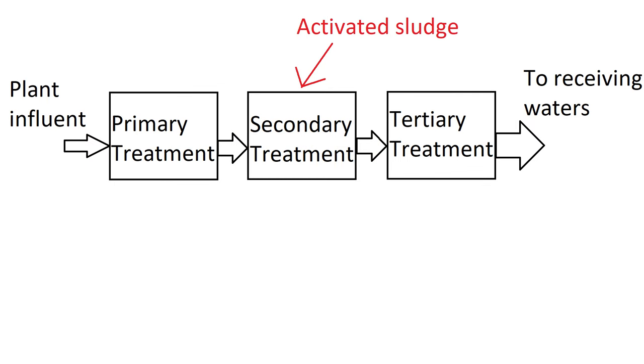Here's a crude schematic diagram of a typical wastewater treatment process that uses activated sludge. This is a secondary treatment operation, meaning that some degree of primary treatment is necessary to remove gross debris, grit, and some of the easier-to-remove pollutants before the waste stream hits the activated sludge tank. Additionally, in a municipal setting, there's probably a permitting program that requires significant industrial users to do some sort of pre-treatment on any wastewater that leaves their facility.